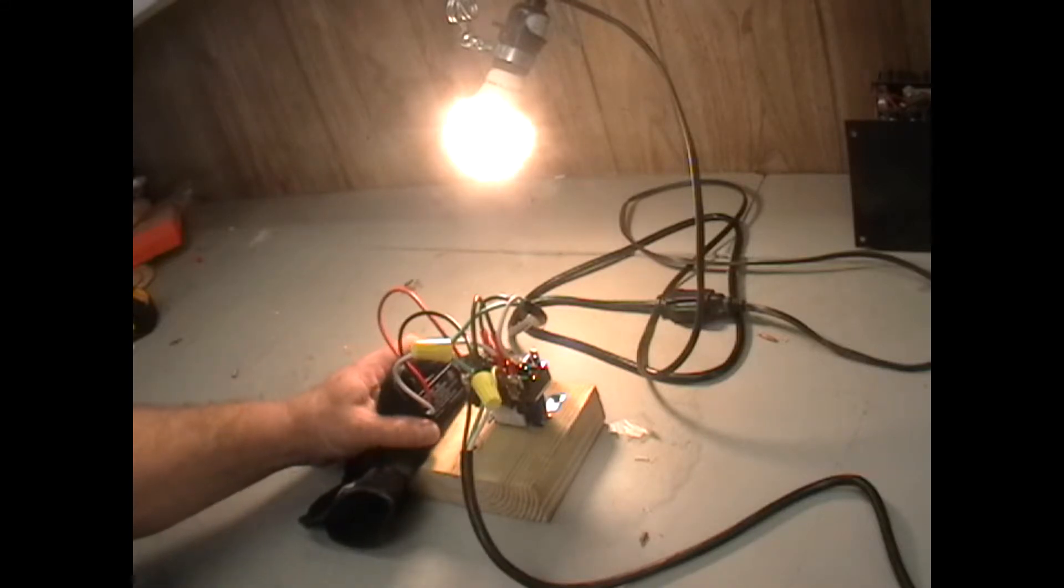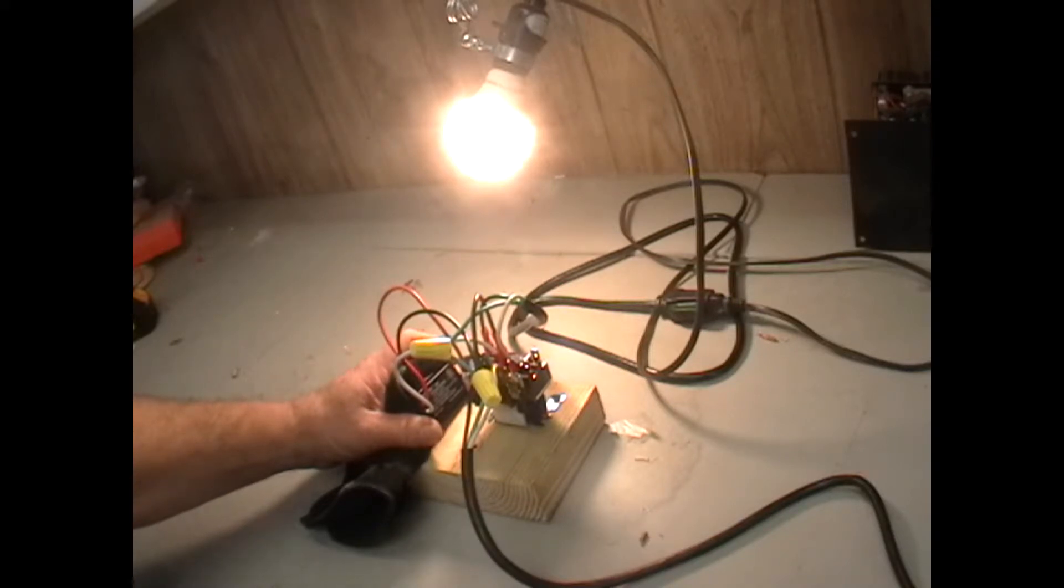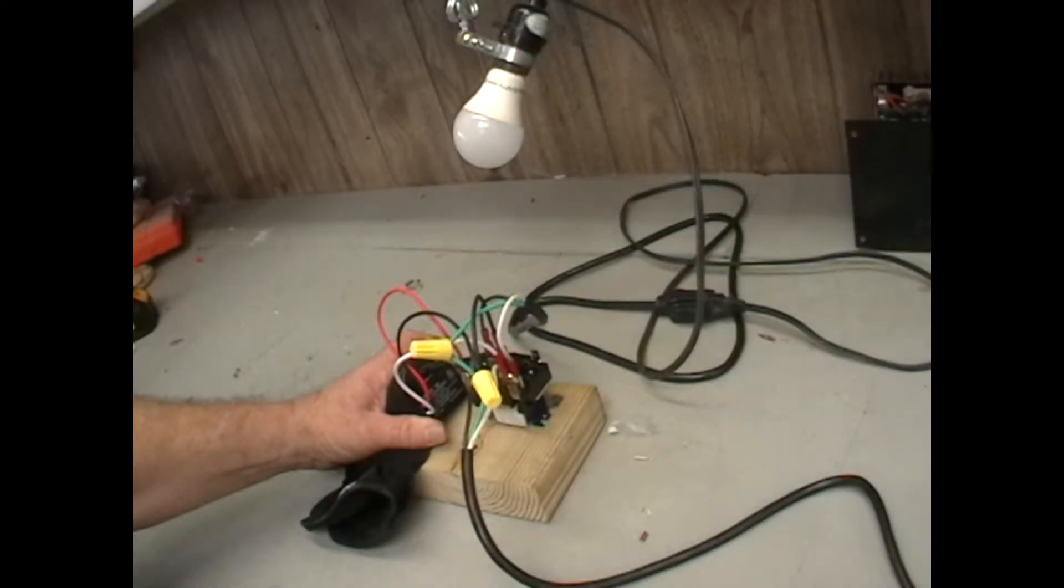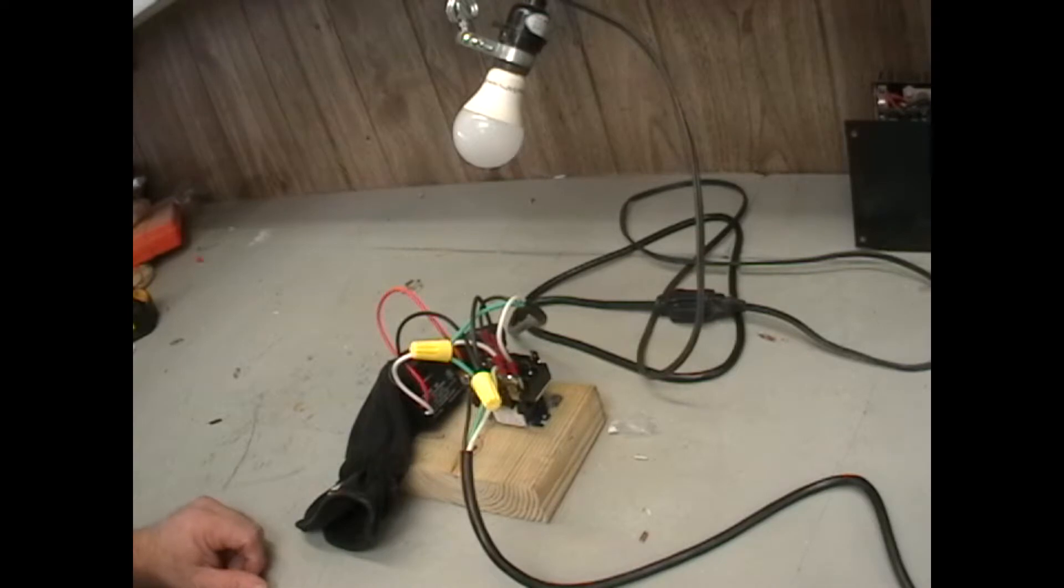So we've had our glove over here on this photocell for a few seconds, and shortly this bulb should go off as soon as the photocell makes, and there it goes, and it's dark, our pumps went off.